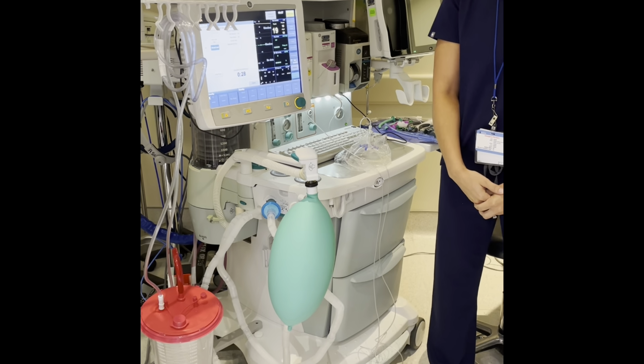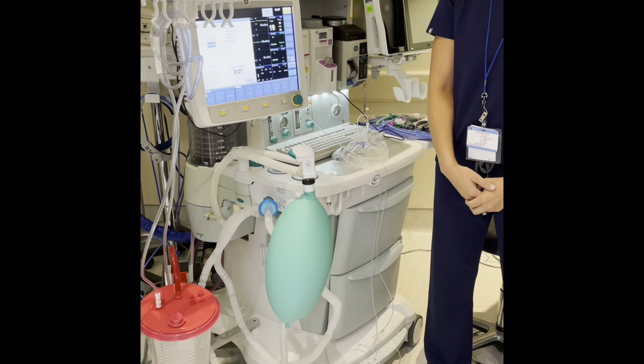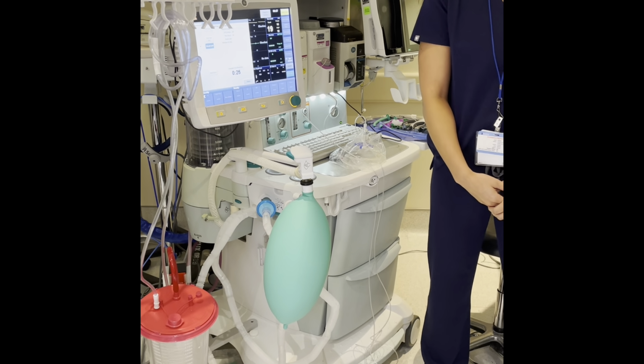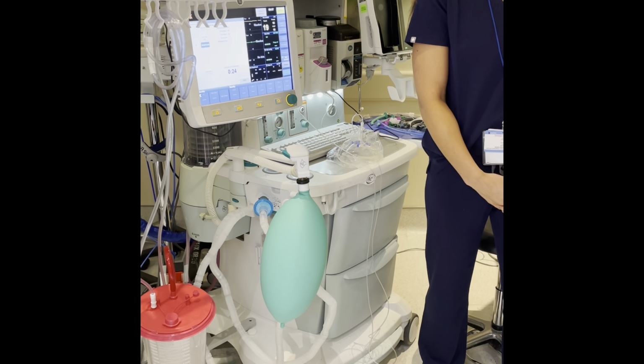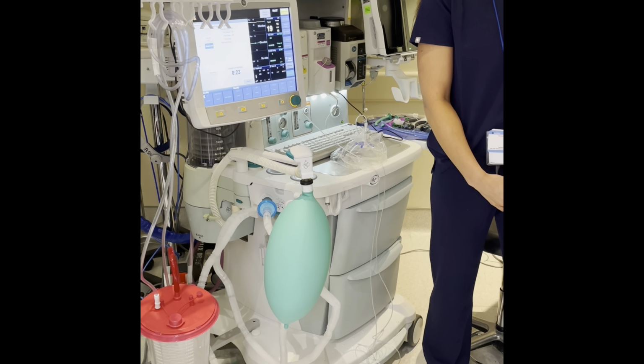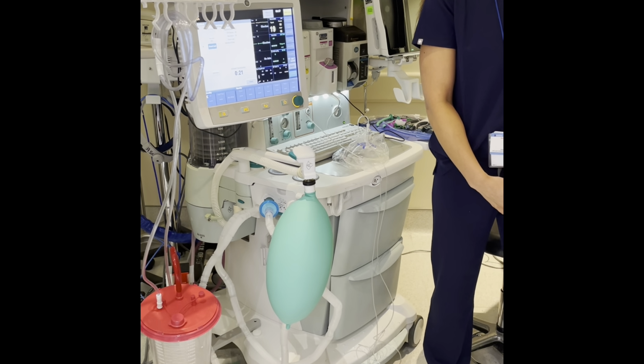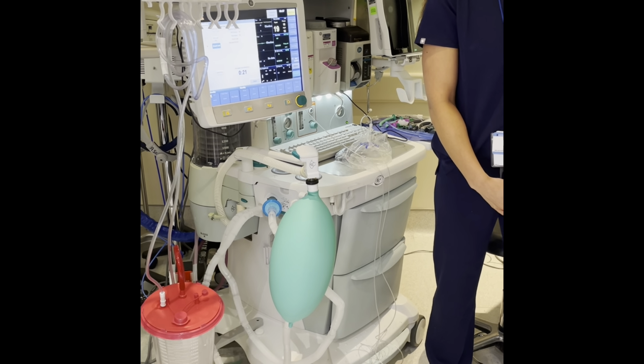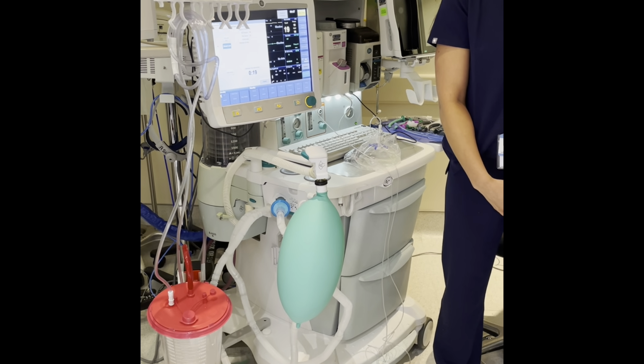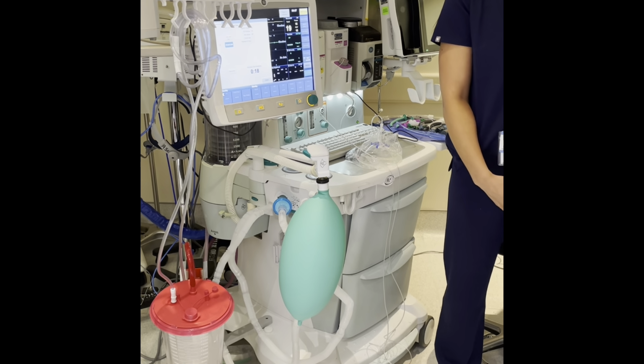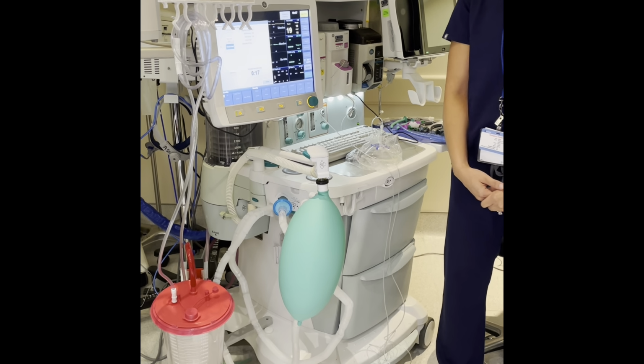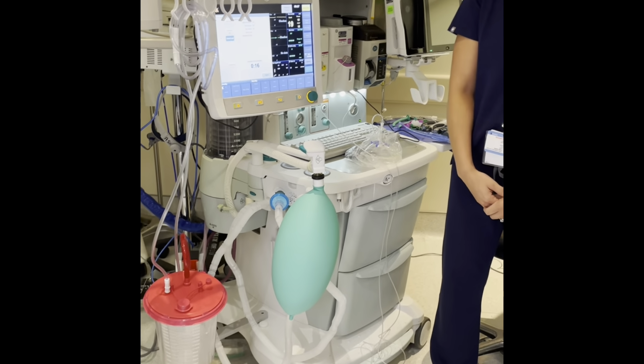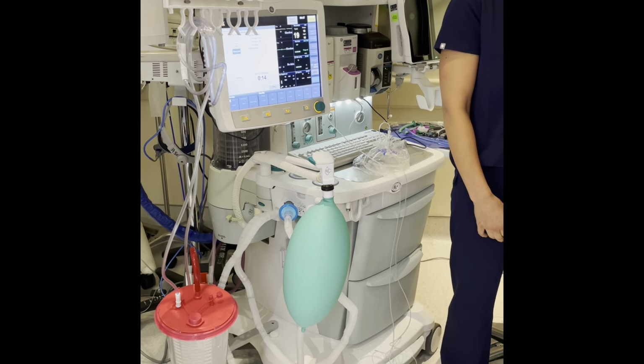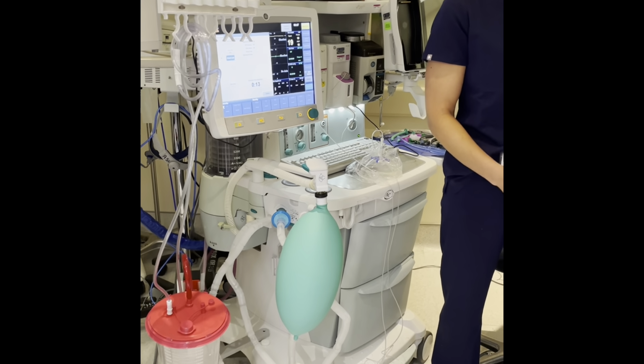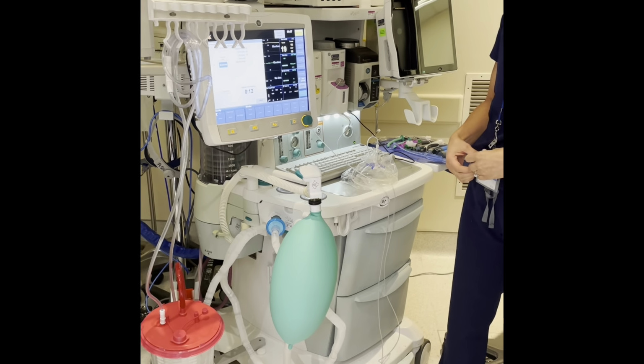What is the APL valve for? It stands for adjustable pressure limit, and it helps to divert gas to the scavenging or pressurize the system when you're trying to manually ventilate the patient. So we can go through that in a little bit more detail as well. As we go through the machine, we'll talk about all of that, okay? Because we go from the different pressure systems all the way to where you get gas to the patient. Okay.